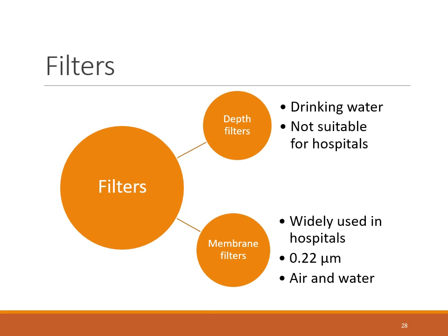Then filters are mostly of two types. One is depth filter and another is membrane filter. Depth filters retain particles throughout the depth of the filter rather than just on the surface. They are used as drinking water purifiers. They do not achieve sterilization and are not suitable for hospital use.